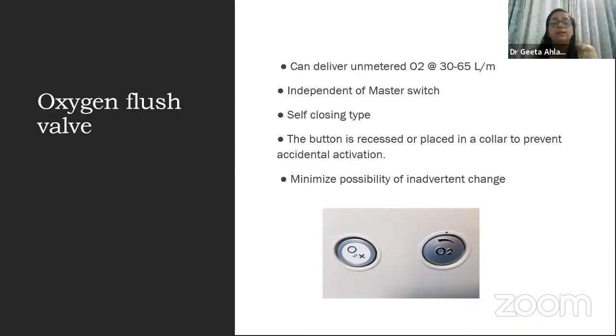It must have saved you many times when you have made some mistake of not changing the knob to the bag or the ventilation type, and still you've started inducing, or there is some problem with the machinery, or adequate help is not available, or you're a single person stuck in some situation. This is our biggest savior, and it should be ensured and checked thoroughly before taking up the machine.